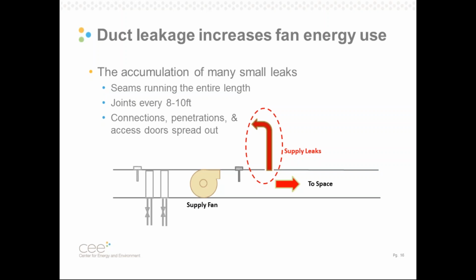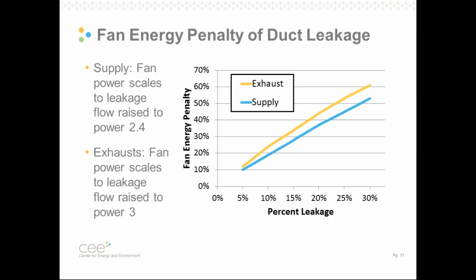And remember, this is the accumulation of small leaks. It's seams that run the entire length, it's joints you find every 8 or 10 feet, and it's the connections, penetrations, and access panels you find throughout the system. And even these small leaks have big energy penalties. If you are aware of the affinity laws, you know that power scales with flow rate cubed. So even small changes in flow rate or duct leakage result in significant increases in fan power.